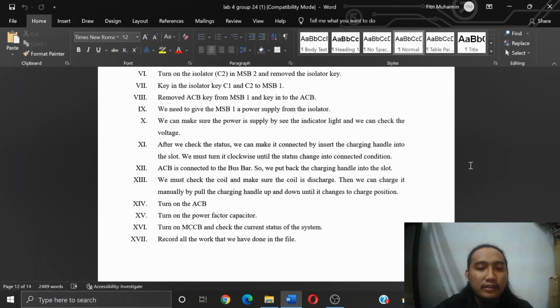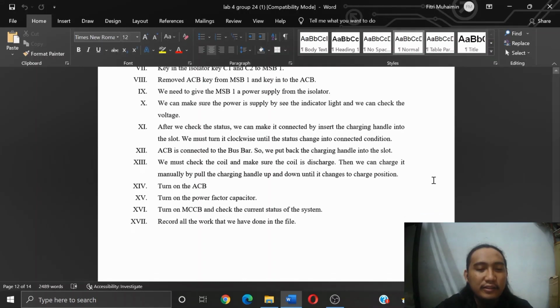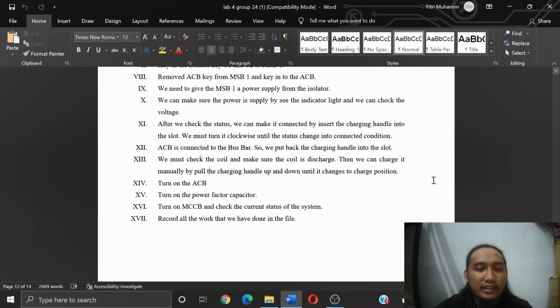Next, we must check the coil and make sure the coil is discharged. Then we can charge it manually by pulling the charging handle up and down until it reaches the charged position. Then we can turn on the ACB. Next, we turn on the power factor capacitor first. Then we turn on the MCCB or load and check the current status of the system. So the MSB is already ready to use. And lastly, we need to record all the work that we have done in the file.